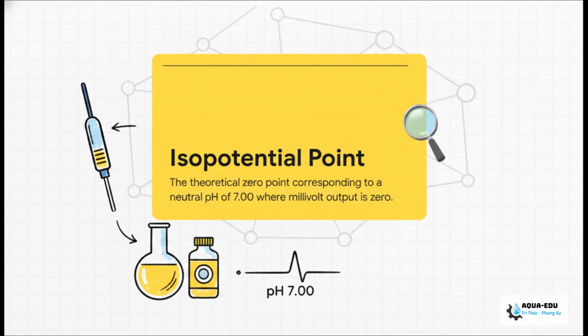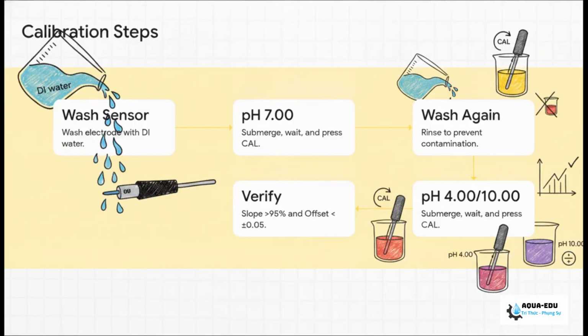That's your anchor. And it's exactly why the very first buffer solution you use for your calibration is always going to be that yellow pH 7.00 bottle. Now you must follow this calibration flow to the letter. First, wash the electrode gently with deionized or DI water, then submerge it in your yellow pH 7.00 buffer. Give it 1 to 2 minutes for the signal to stabilize, and hit CAL to set your 0 point.